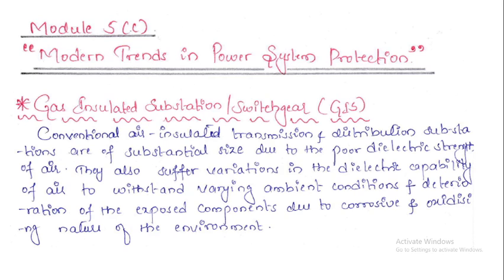Conventional air insulated transmission and distribution substations are of a substantial size due to the poor dielectric strength of air. As we already learned, having visited various substations, the size of the substation is very large. It requires a huge area for the construction of these substations. They also suffer variations in the dielectric ability of air to withstand varying ambient conditions, and deterioration of the exposed components due to the corrosive and oxidizing nature of the environment. As these substations are directly exposed to the environment, because air is acting as an insulating medium, they may suffer from corrosion, or there may be a problem of oxidation.